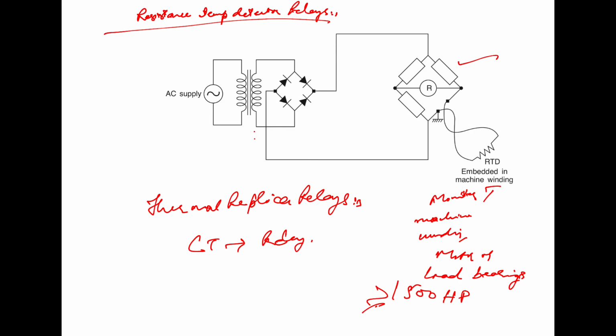Now the thermal replica relay is recommended when the temperature detectors are not available. So these relays are used when the temperature detectors are not available. Otherwise, we use the resistance temperature detector relays. Replica relays are typically temperature compensated and operate in a fixed time at a given current, regardless of ambient variations, as compared to the RTD. Although this characteristic is desirable, it also provides under protection for a high motor ambient and over protection for a low motor ambient. So this type of relay can be used only when the resistance temperature detectors are not available.